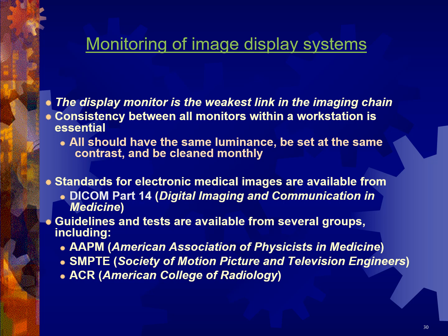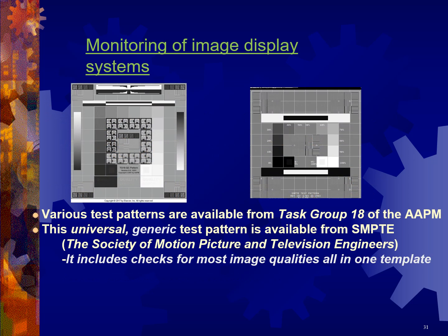Various test patterns exist. The two most common are the TG18 by the American Association of Physicists in Medicine, and the SMPTE test pattern, which is probably the most popular, but the TG18 is specifically designed for medical imaging display systems. All right, so these are the two test patterns. The one on the right is the SMPTE. The one on the left is the Task Group 18 or TG18 from the AAPM.